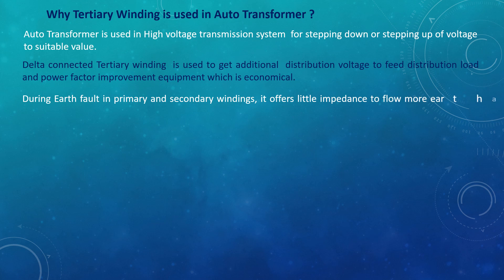Why is tertiary winding used in an auto transformer? An auto transformer is used in high-voltage transmission systems for stepping down or stepping up the voltage to a suitable value. A delta-connected tertiary winding is used to get additional distribution voltage to feed distribution load and power factor improvement equipment, which is economical. During earth fault in primary and secondary windings, it offers little impedance to allow more earth fault current to flow for operation of the protective relay.